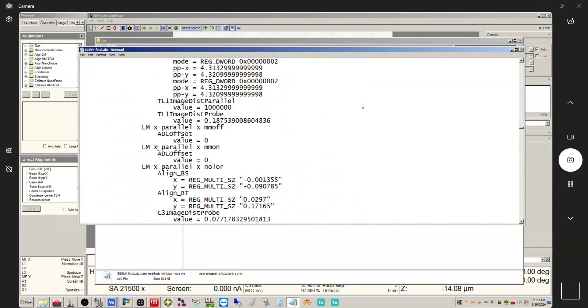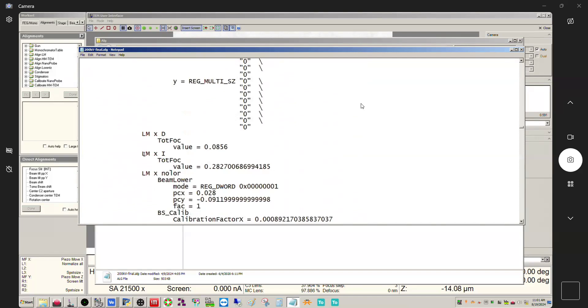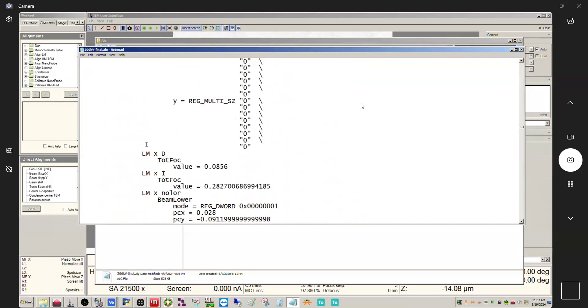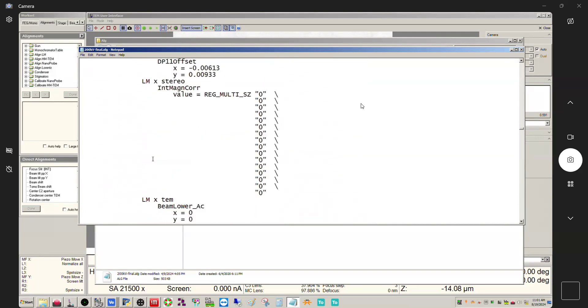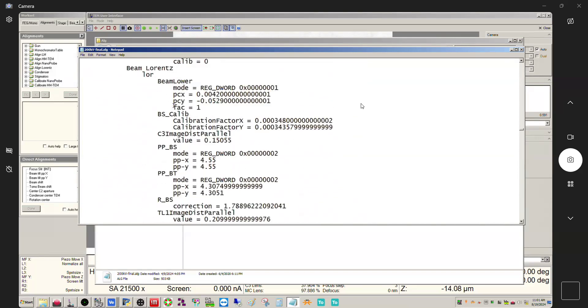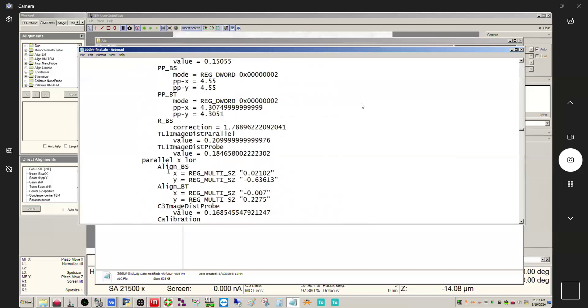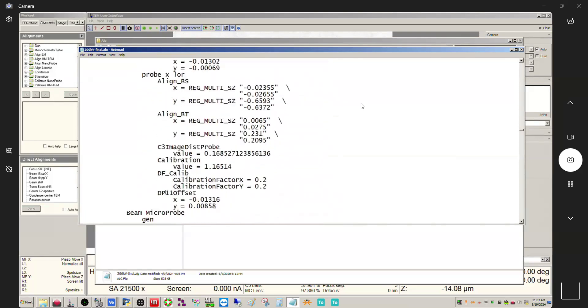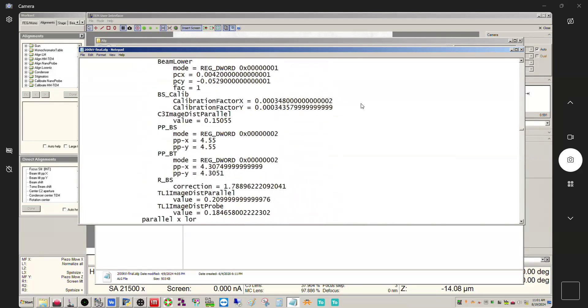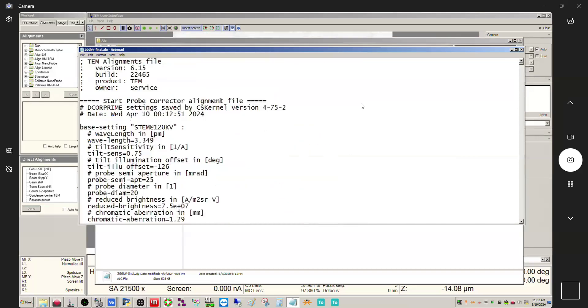You can see now here's, this is for LM mode right, since we already did that, we did align LM. And again right, so there's values here for the pivot points, there's values here for your different deflectors right. So that all gets set into this alignment file. We don't need to belabor this, this is just what happens when you save the file, so you can have an appreciation for this.